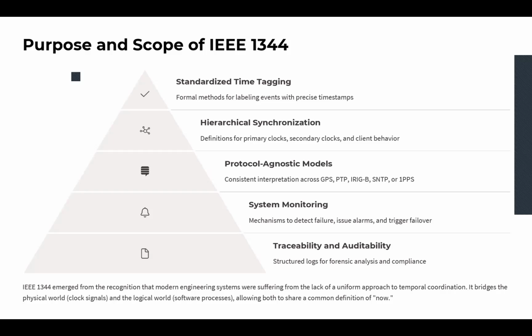So these time tags allow us to correlate data from diverse sources. For example, a phasor measurement captures a measurement at a certain time, with a known accuracy. If we tag that with a precise, traceable timestamp, then that measurement would not be ambiguous, and we could verify it, and we could trace the data, the measurement, and the action that we had based on that measurement through our log history.